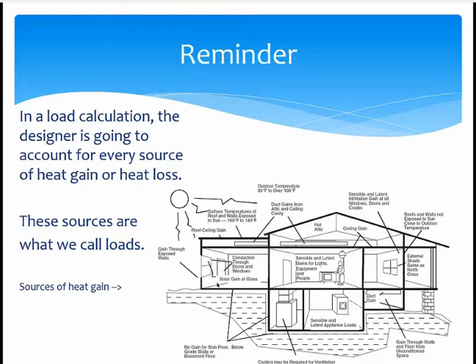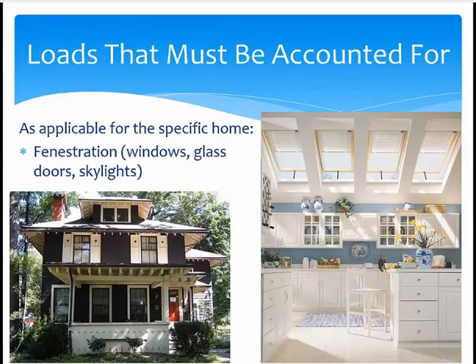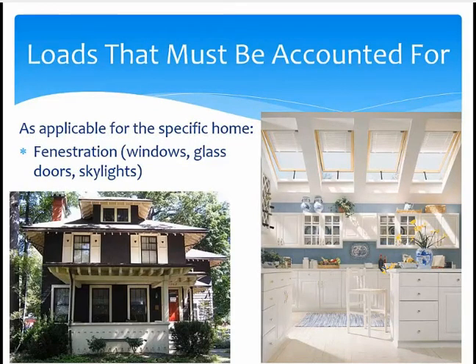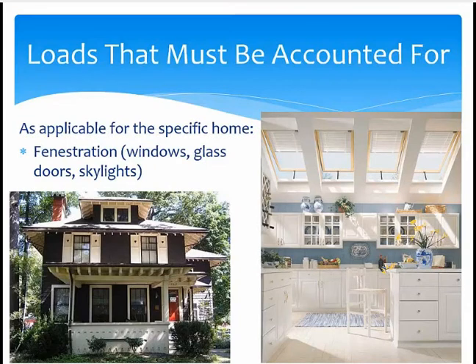Now let's look more in depth at the various loads included in a normal load calculation. The first are the loads that will likely have the biggest impact on the final load calculation, and those are the loads due to fenestration — loads that come from windows, glass doors, and skylights. It makes sense: if you sit next to a window in the middle of winter, you'll feel colder than anywhere else in the room because heat moves through glass so easily. A window will lose more heat than a wall, wooden door, or ceiling.